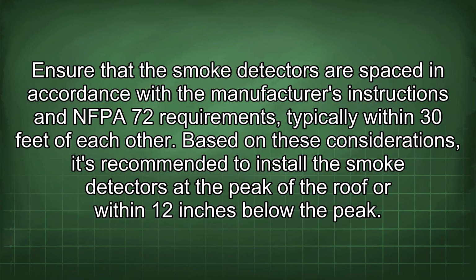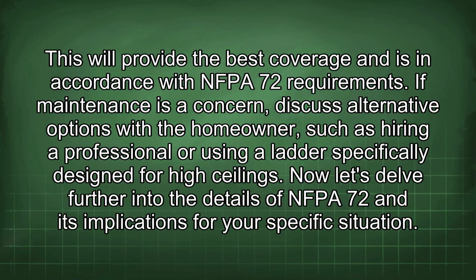Based on these considerations, it's recommended to install the smoke detectors at the peak of the roof or within 12 inches below the peak. This will provide the best coverage and is in accordance with NFPA 72 requirements. If maintenance is a concern, discuss alternative options with the homeowner, such as hiring a professional or using a ladder specifically designed for high ceilings.